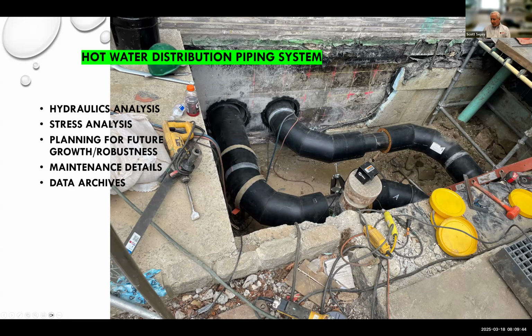The pressure and load profiles of your campus or building systems inform the material selections, the pipe sizing, and the routes. At the top of our campus, which has higher elevations and lower pressures, we may end up using plastic piping, but we're not there yet. We use EN 253 steel piping at the plant and the lower parts of the campus, which we've already built. This piping is pre-insulated and only the weld joints are field insulated, which you can see on the slide.